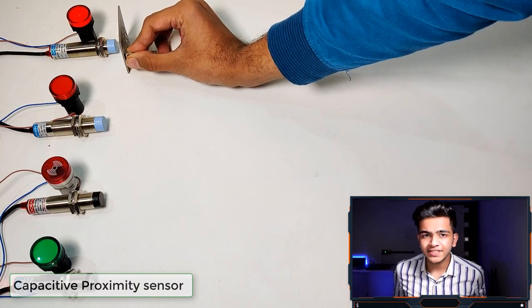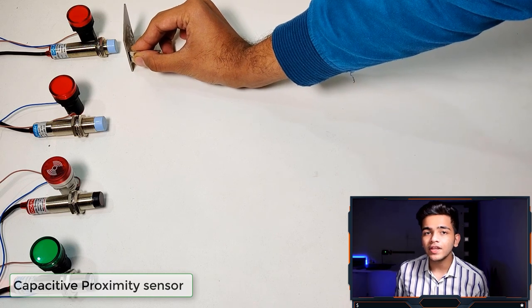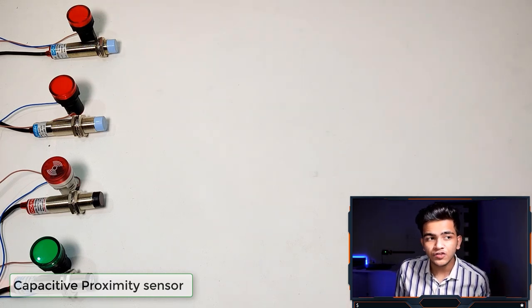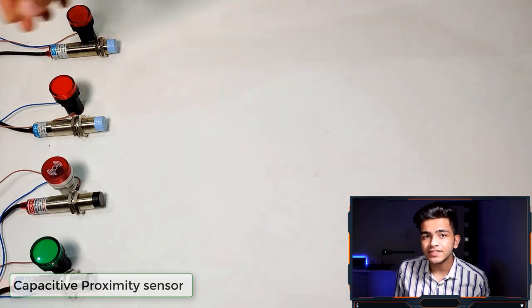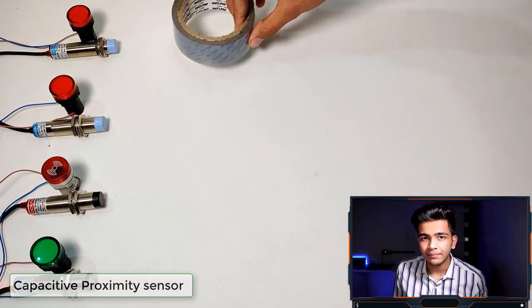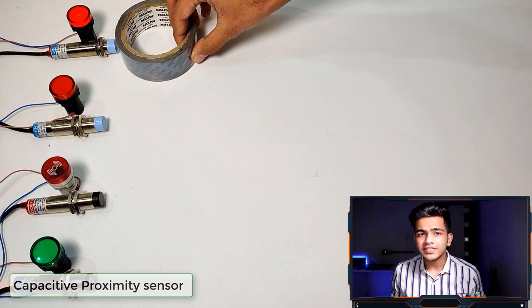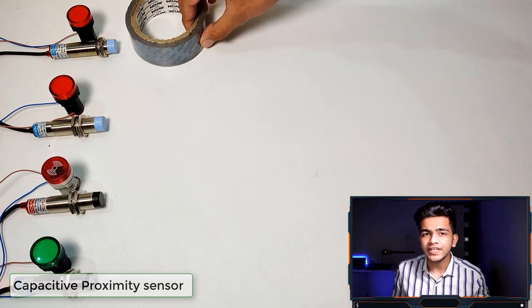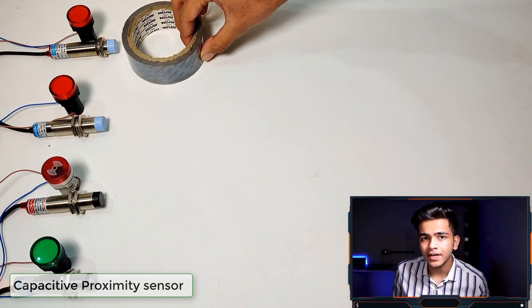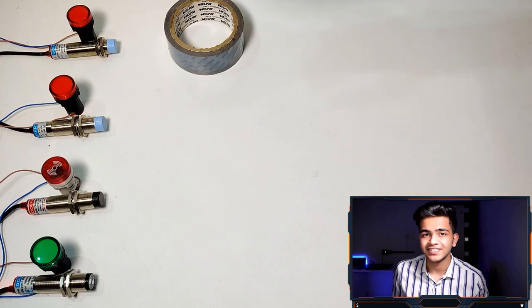As the diameter of the sensor increases, the sensing range also increases. Usually the range of a capacitive sensor is about 2 mm to 15 mm, but in automation you can also change the sensing range using a sensitivity adjustment at the back of the sensor.